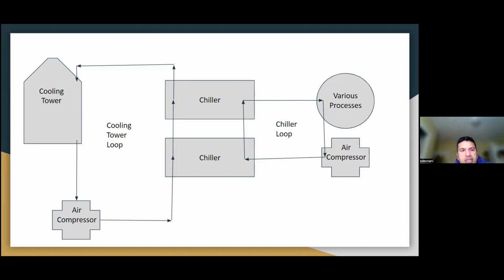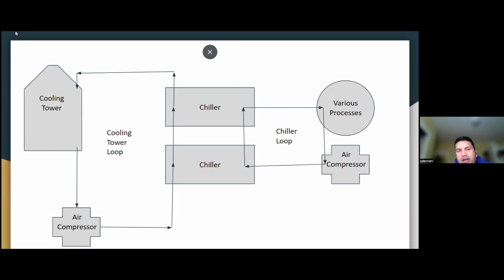For heat rejection, you need 3 GPM per ton on the cooling tower side. So you're moving 2.4 in the chiller loop, and 3 GPM in the cooling tower loop. If you have your pump size, and let's say your pump gave you 250 GPM on the chiller loop, then I can by default tell you that your chiller is approximately 100 tons each. See that dirty little trick? Now, if I know that the condenser water pump was 300 GPM, I also can deduce that it is 100 tons on the chiller side.